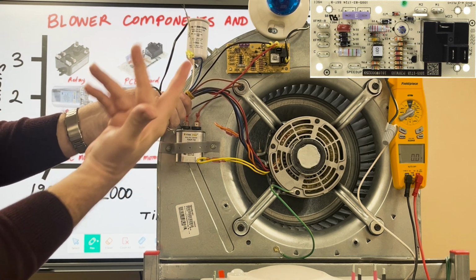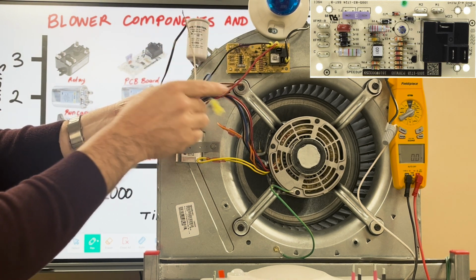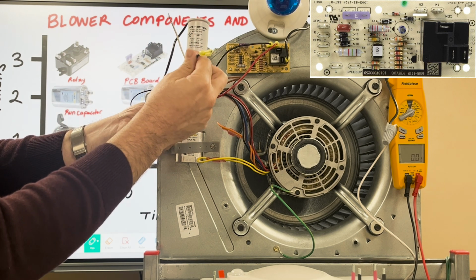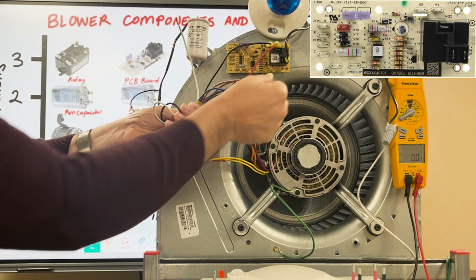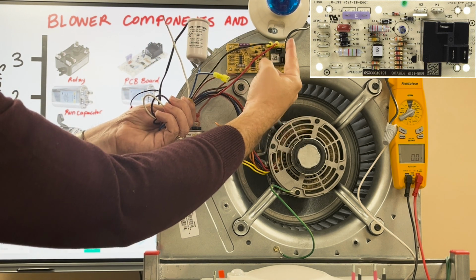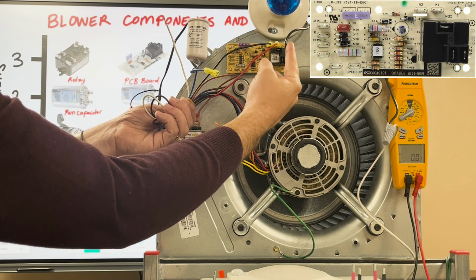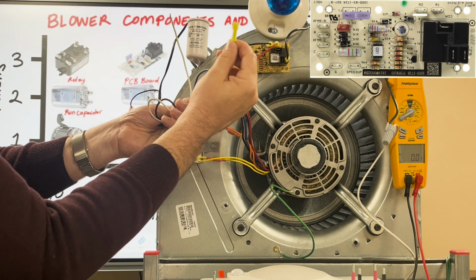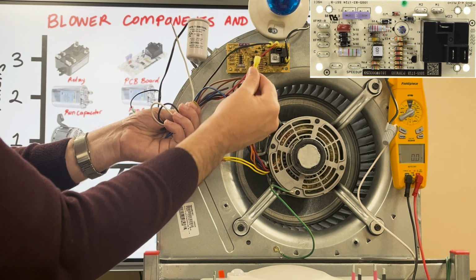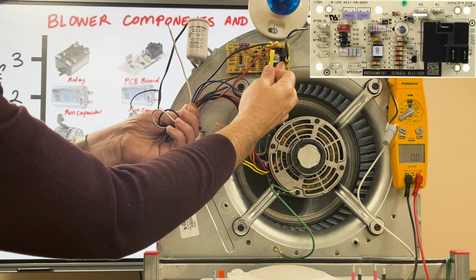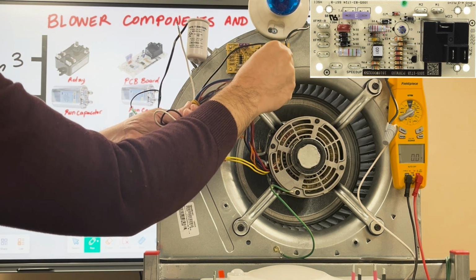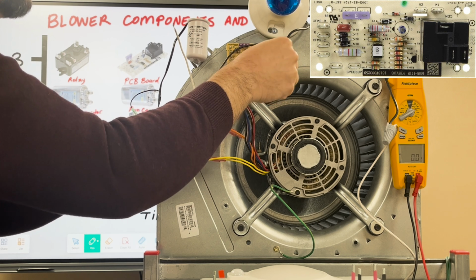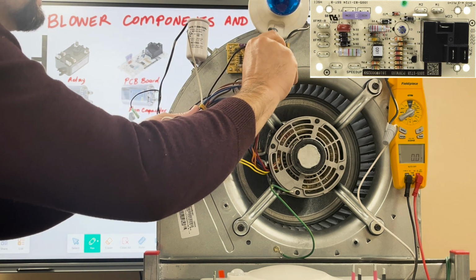So now it's pretty simple. I need to put a leg of power here and a leg of power here. My medium speed, I'm going to break that across my relay. I already demonstrated this is my normally closed portion of the relay, so I'm going to wire my medium speed tap over to the normally open, and push that on there.